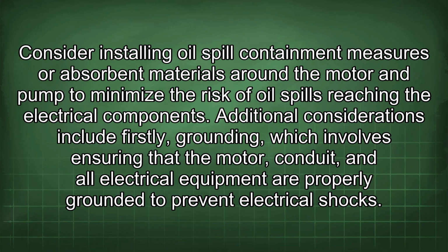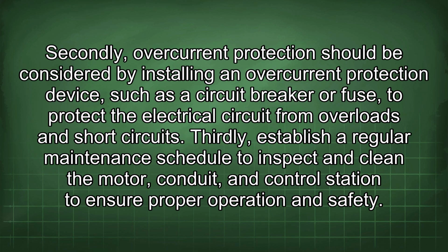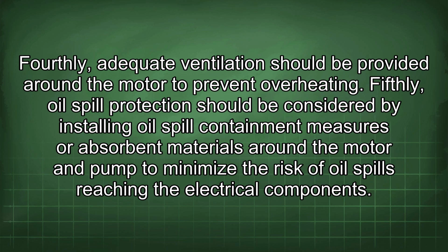Additional considerations include, firstly, grounding, which involves ensuring that the motor, conduit, and all electrical equipment are properly grounded to prevent electrical shocks. Secondly, overcurrent protection should be considered by installing an overcurrent protection device, such as a circuit breaker or fuse, to protect the electrical circuit from overloads and short circuits. Thirdly, establish a regular maintenance schedule to inspect and clean the motor, conduit, and control station to ensure proper operation and safety. Fourthly, adequate ventilation should be provided around the motor to prevent overheating.